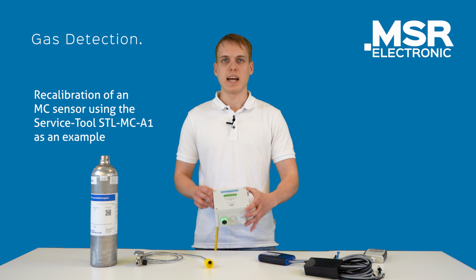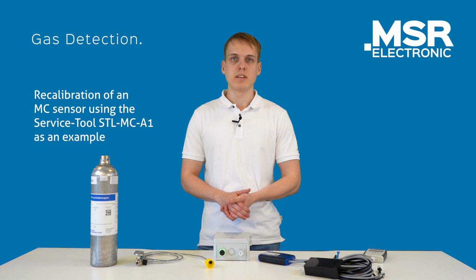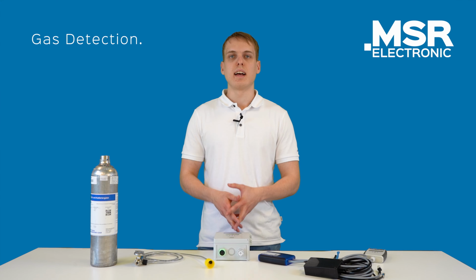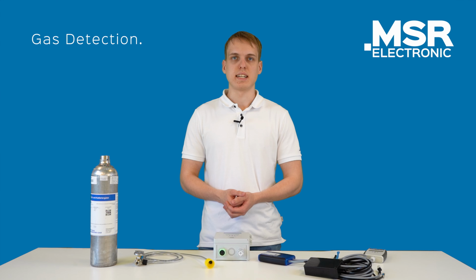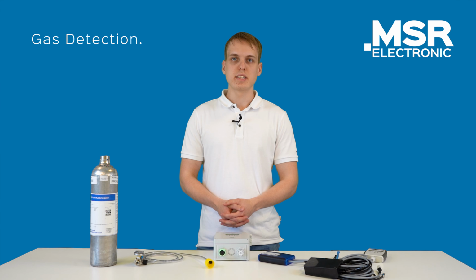Today I will explain to you how to calibrate an analog sensor head by using our gas warning detector MSC2. Before we get started, I would like to ask you to calibrate our gas sensors in regular intervals. Otherwise, we cannot guarantee an accurate measurement of the sensor head. All the information about the calibration process you can find in our user manual under Technical Data.